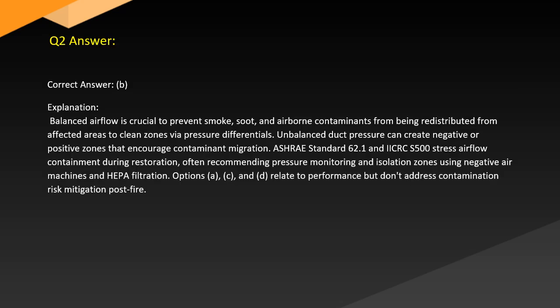Answer. Correct answer: B. Explanation. Balanced airflow is crucial to prevent smoke, soot, and airborne contaminants from being redistributed from affected areas to clean zones via pressure differentials. Unbalanced duct pressure can create negative or positive zones that encourage contaminant migration.